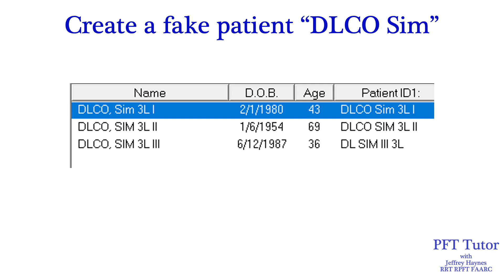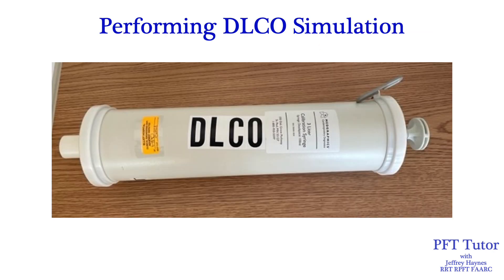In my laboratory, we have three systems, so we had to create three different simulation patients — one for each machine — so we can call them DLCO Sim1, DLCO Sim2, and DLCO Sim3. I use one dedicated 3-liter syringe to perform DLCO simulation on all three systems to minimize the effect of differences between syringes. I'm not sure if that's absolutely necessary — it's just the way I do it. Obviously, if you only have one PFT system, this won't be a problem for you.